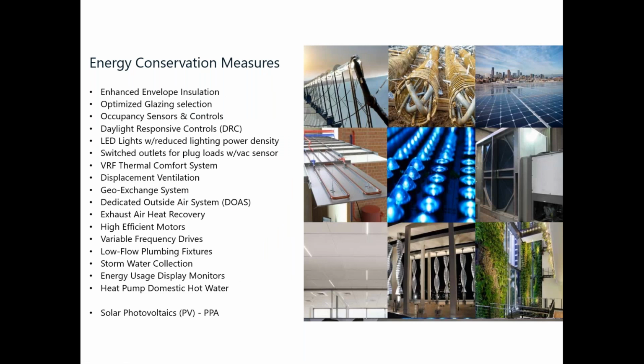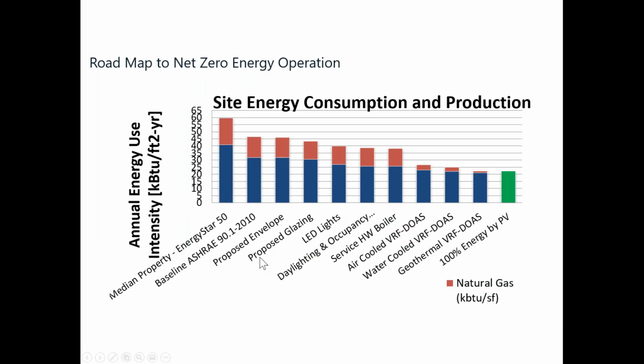Sorry. So this is our roadmap again to net zero energy. And you'll see that a baseline building these days that we would have had to design to ASHRAE 90.1 2010 in DC would have had an EUI of about 46. On the left-hand side, we do all of the building envelopes, LED lighting, service hot water, the VRF system, which is water cooled, and the dedicated outdoor air system with CO2 sensors. And we get our energy use intensity down to about 21 or 22. And then we generate from there. So we have a power purchase agreement in place to generate approximately 22 kBTU per square foot per year for this high school.